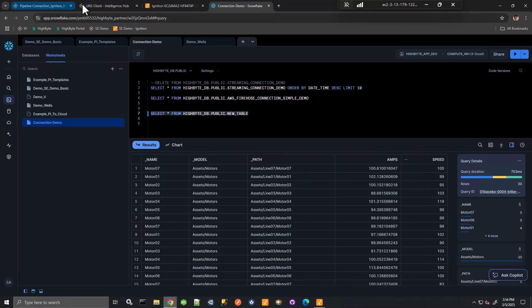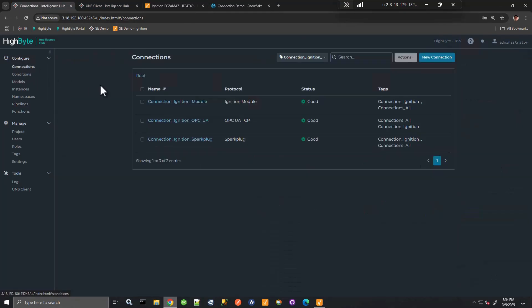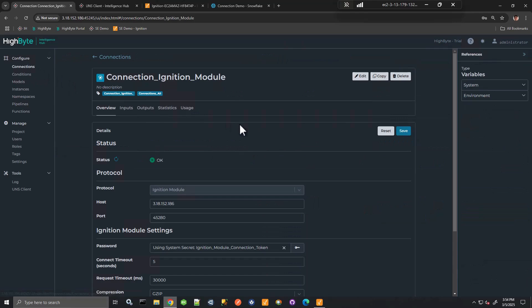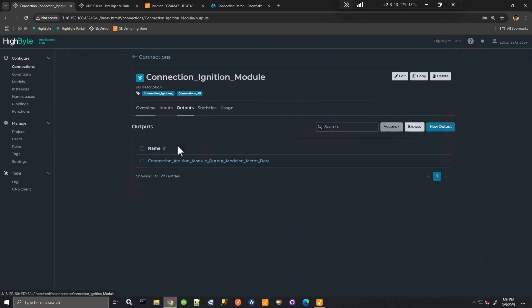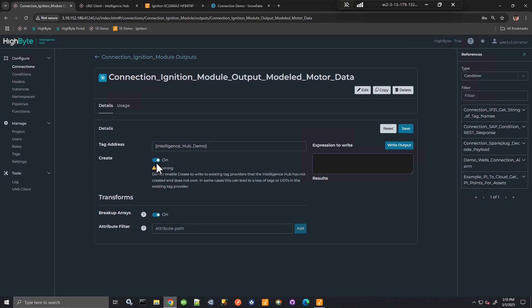So not only can we obtain data from Ignition using the module connection, we can also write to. And this is pretty powerful. So here I can define the tag provider and I can indicate create on. So what we're going to do here is if we have the right syntax providing an underscore name, an underscore model to this connection output, we'll actually create a UDT and also create UDT instances. Obviously, we could turn the create off and just update existing as well.